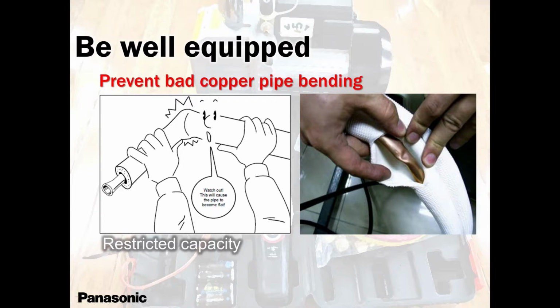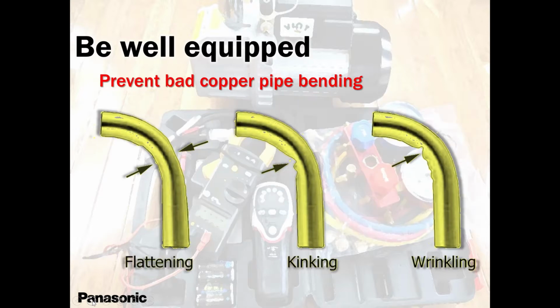But if it's a tight bend, if it's a 90, please use a bender. 90, 70, 80 degrees, you need a bender, guys. 45, maybe you could be okay. Only on 3/8 and quarter inch, you are fine. But guys are using their hand even with 3/4, a half inch, and 5/8. That's dangerous. You can waste your time there. So please, once again, benders crucial. Benders important.